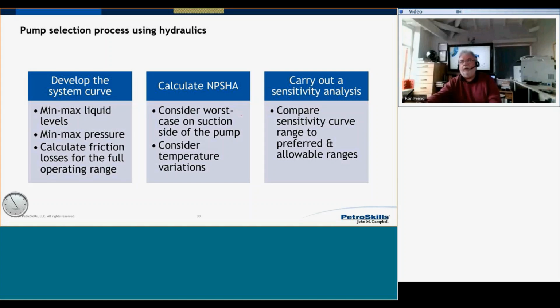The learning points here. What do we actually do? Well, you've developed a system curve, but remember, you need to consider your minimum and maximum liquid levels, your minimum and maximum pressure. Calculate the friction losses for the full operating range.